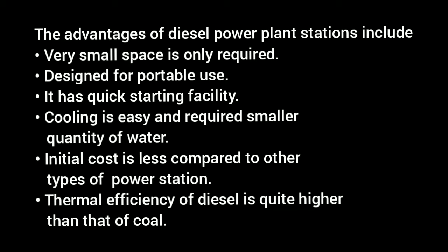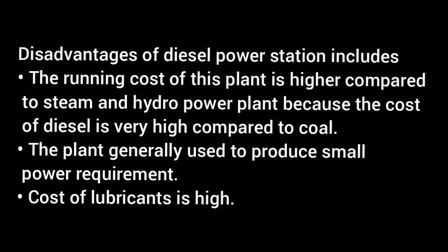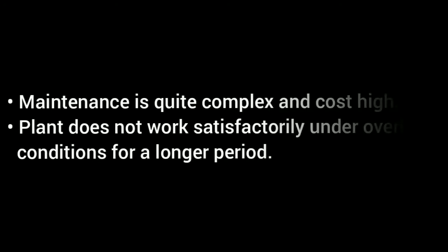Then let's discuss about the disadvantages. The running cost of this plant is higher compared to steam and hydropower plants because the cost of diesel is very high compared to coal. The plant is generally used to produce only small power requirement. Cost of lubricants is high, maintenance is quite complex and costly. Plant does not work satisfactorily under overload conditions for a longer period.